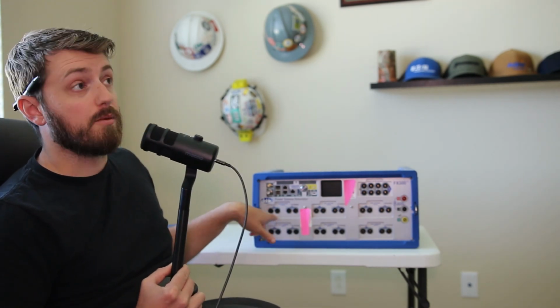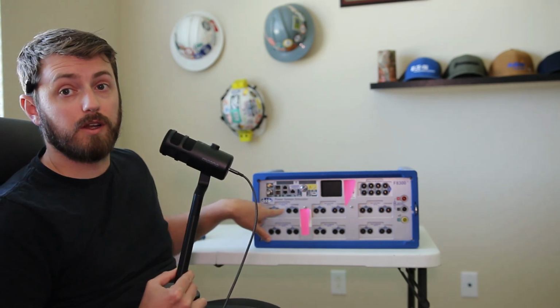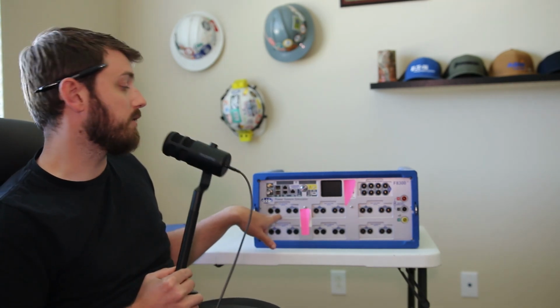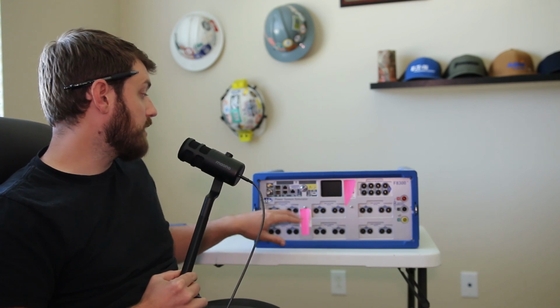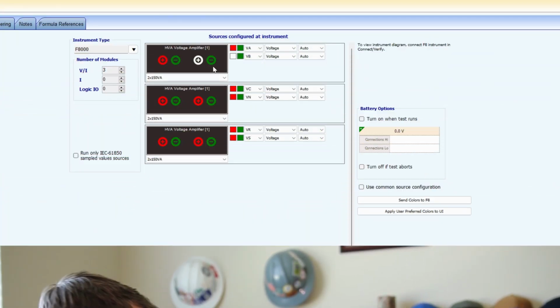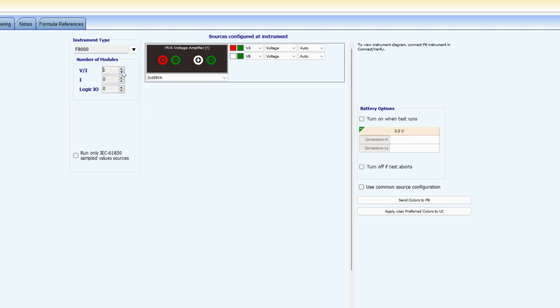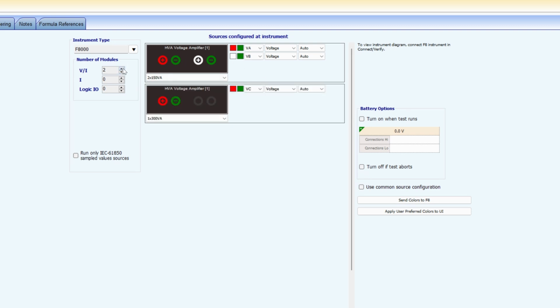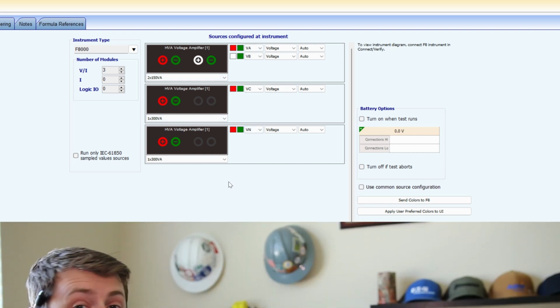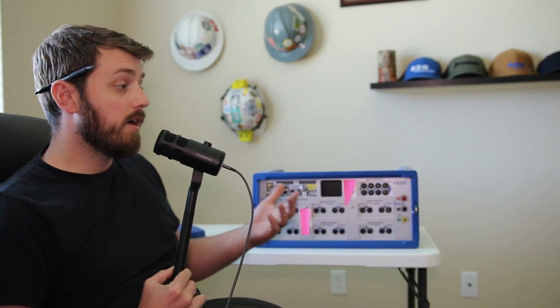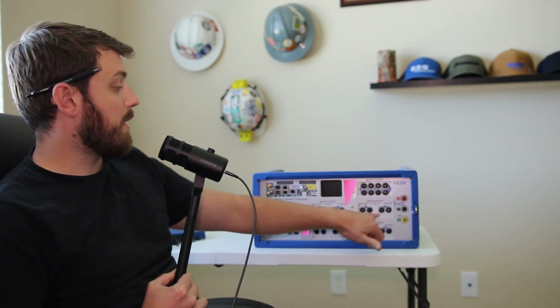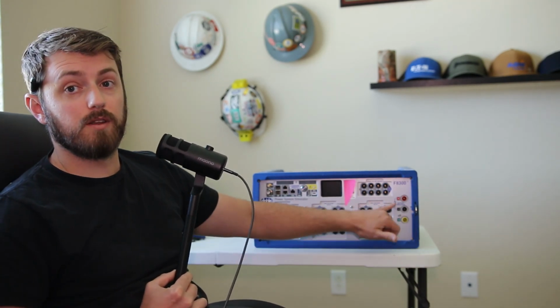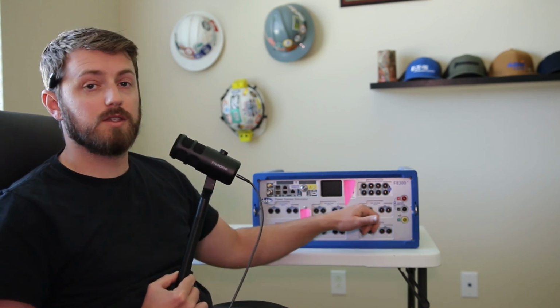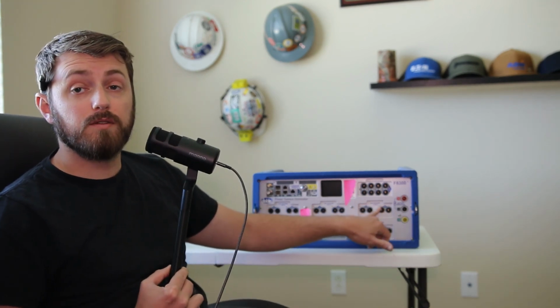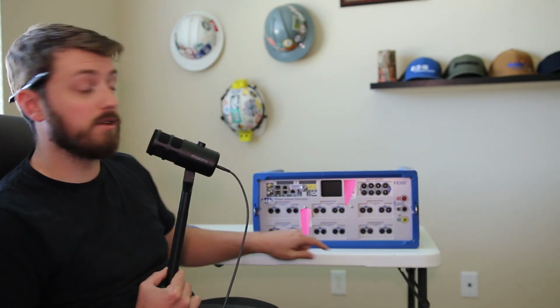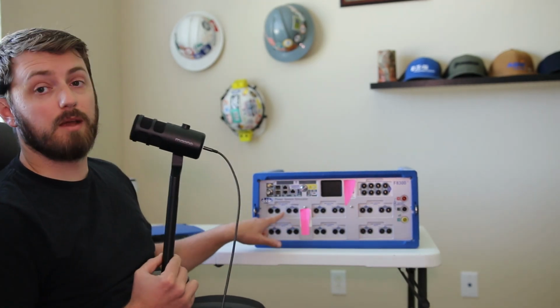Now, in the control panel setup, or the default configuration setup you can do in Protection Suite, I'll put a screenshot of it up. I can turn these off and just use the currents, except I needed at least one voltage channel for what I was doing, and it was the first module that was disabled. So they wound up telling me, oh, you can pull this module out and swap it with this one, then mask off whatever the number 5 and 6 channels would be in the voltage. You can turn those off in Protection Suite, and so you ignore your bad module and use a good module that has to be enabled. This first one has to be enabled.